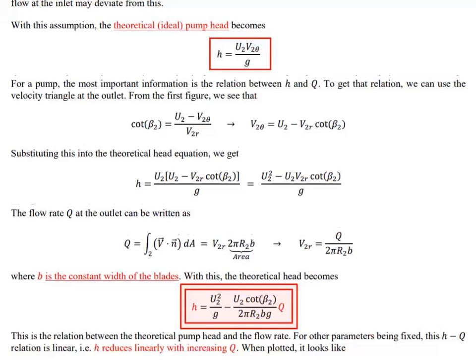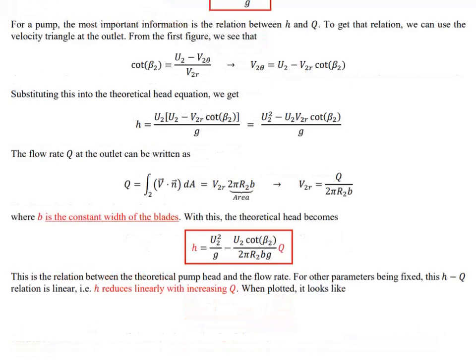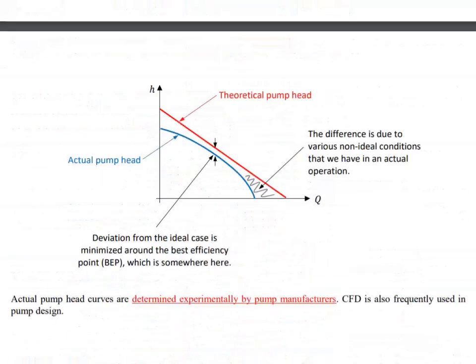Again, you need to follow the details that we skipped here by yourself. As you see, for a given pump with known dimensions rotating at a certain speed, the H-Q relation is linear. The relation is also sketched as you see. Pump head starts from a maximum possible value and drops linearly with Q. To pump more liquid, we need to sacrifice from the pump head.